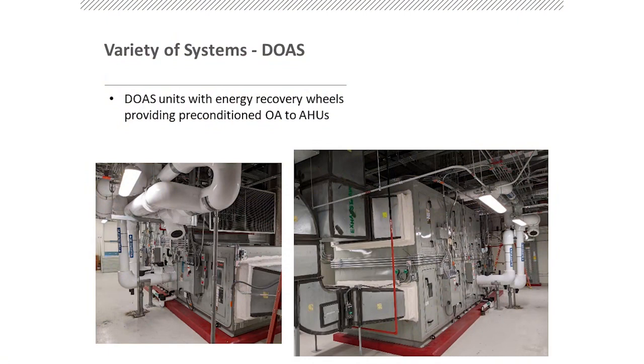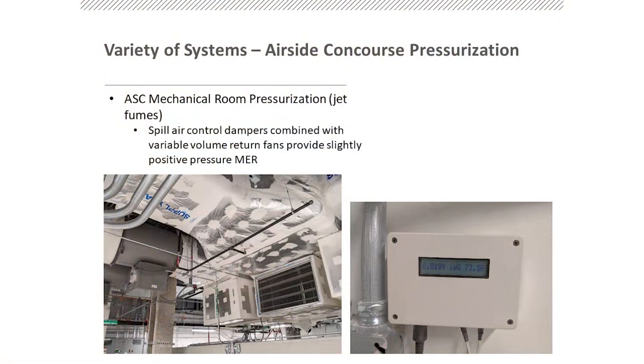Dedicated outdoor air, it's Central Florida, very hot, humid climate. It really made sense to incorporate dedicated outdoor air systems. There's energy recovery wheels within these units, and basically they provide preconditioned air to the air handling units that decouple the latent load for the outdoor air from the sensible load, and just helps all the systems operate more efficiently. Not necessarily unique to an airport, but a very good feature they incorporated.